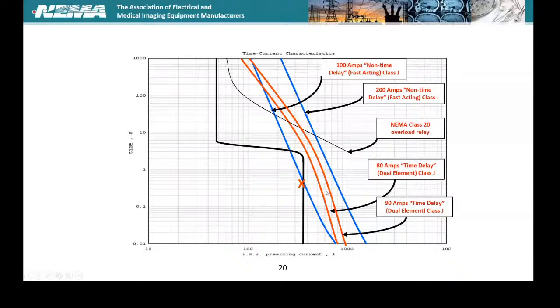This really does a good job of showing, too, the difference between a fast-acting versus a time delay fuse. All of these are Class J fuses, but the curves are considerably different between a fast-acting fuse and a time delay. You would not want to use a fast-acting fuse on anything like a rotating motor or a transformer with transformer inrush. Fast-acting fuses are used primarily in places like data centers and on loads that aren't going to draw that inrush current. So that time delay and the shape of that fuse curve is critical to help you ride through that few cycles of inrush current on such things as motors and transformers.